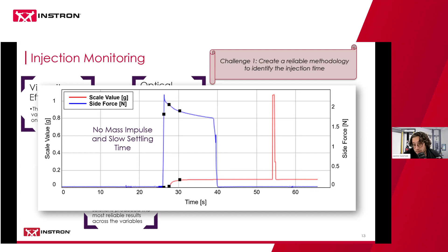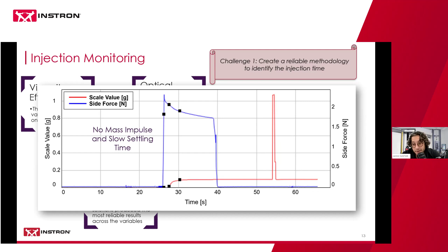If you were to look at an extremely high viscosity fluid, and I apologize, in this graph the scale is in red, you can see that there's almost no impulse whatsoever, and then it slowly settles towards a point. So you can imagine that trying to repeatably measure both of those with the same level of accuracy can be difficult. What we've implemented with the camera system is simple: we have a detection zone where we're looking for fluid. Once we see fluid cross this detection zone, we start a timer. Then we set an operator-defined break timer that says how much time between fluid detection triggers, okay, my injection's over. Just for example, by default, it's typically set to 1.5 seconds.